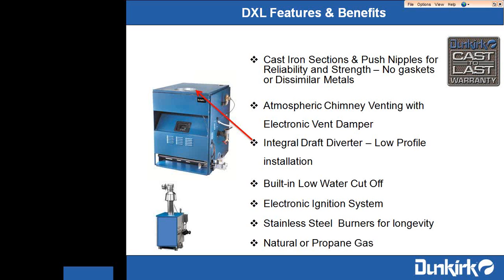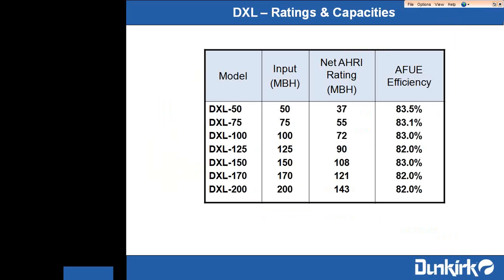Additionally, there were DOE compliance changes that every boiler manufacturer had to comply with as of September 2012. There are a variety of controls that each manufacturer could choose to utilize to achieve the reset that the government requested. We're using the hydro-level hydrostat control, and one of the features it gives us is a built-in low-water cutoff. So your contractors don't need to buy an external low-water cutoff with this boiler. It's there already. The DXL is manufactured in size ranges from 50 through 200,000 BTUs, and again with a minimum AFUE of 82%.